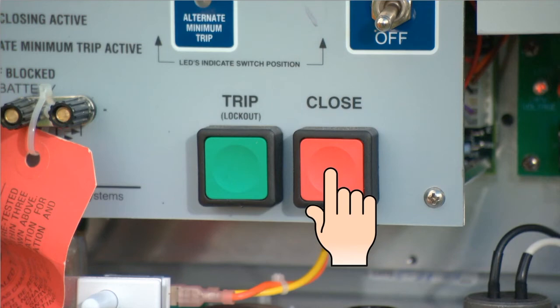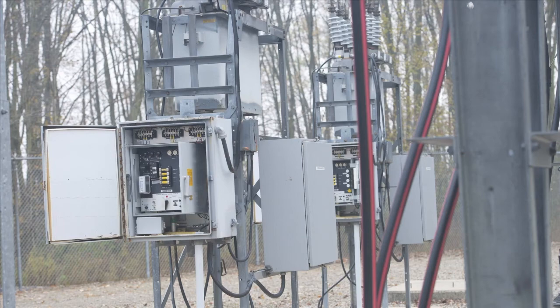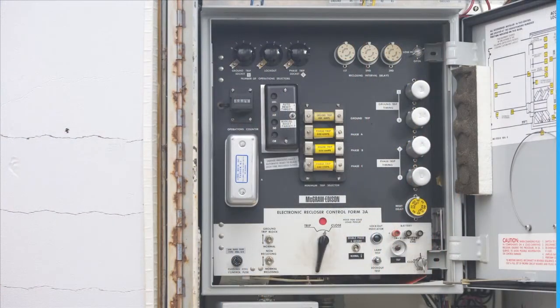While the switch is in the close position, the control is still free to trip and lock out if closed into a fault. The first version of electronics used in controllers were the Form 3A. The Kyle Type ME Form 3 or 3A electronic recloser control are comprised of a number of programmable, solid-state electronic circuits that perform the command functions involved in automatic recloser operation. It is used to operate all Kyle electronically controlled reclosers.